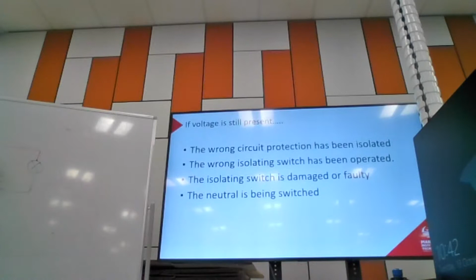That makes sense. And you get weird stuff like when you get broken neutrals. That's what you'll generally find: if the neutral's broken, you'll get weird 230 volts where you didn't expect it. Often you'll pick that up by getting 230 volts between neutral and earth. Because if I test the neutral here to earth, I'm going to have a live voltage, right? Even though that's broken or switched. Cool. Doesn't happen very often. People don't often switch neutrals.